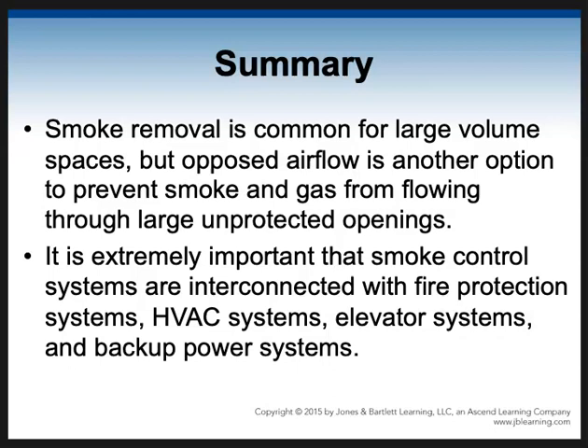The smoke and gas need to be kept from flowing from one part of the building to another part, so they use them to do that. It's extremely important that smoke control systems are interconnected with the rest of the fire protection systems and the HVAC and the elevator systems and the backup power systems. So depending on what systems are involved, some things we're turning off, some things we're turning on. All of that is done by the alarm control panel. So we need to make sure we've got all adequate equipment and that it all works together. It can be really, really, really complicated.